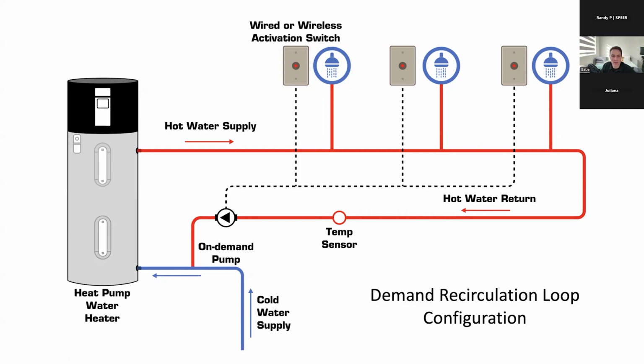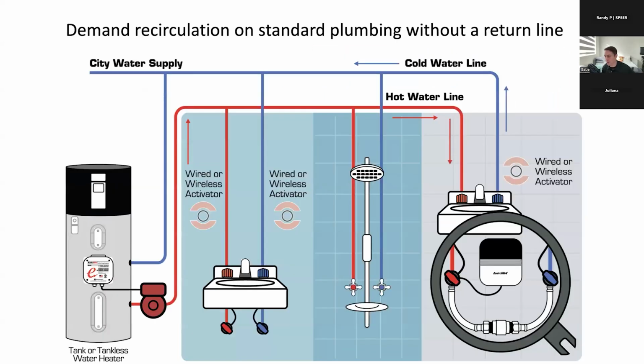So instead of pumps that are running on a timer that could be running for 4, 8, or 12 hours per day, an on-demand system typically only sees about 10 minutes of runtime per day total. But you get all of the advantages of fast hot water on demand.